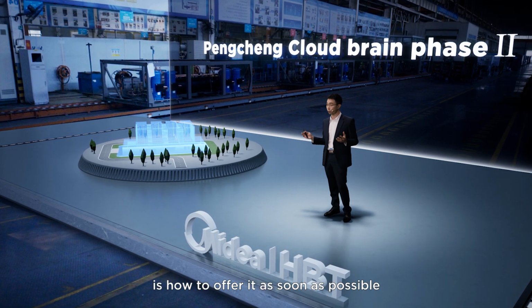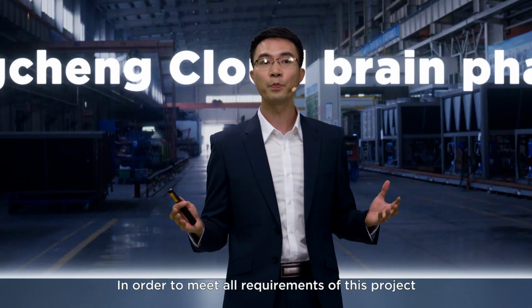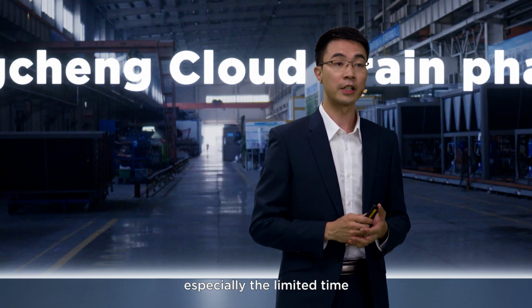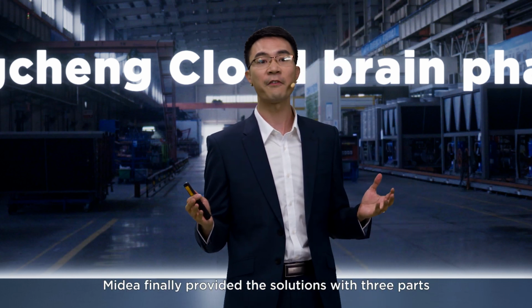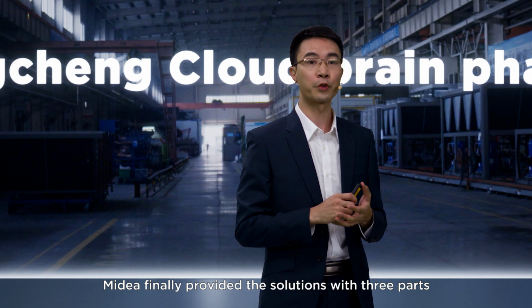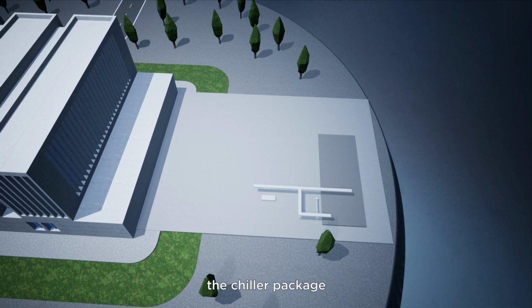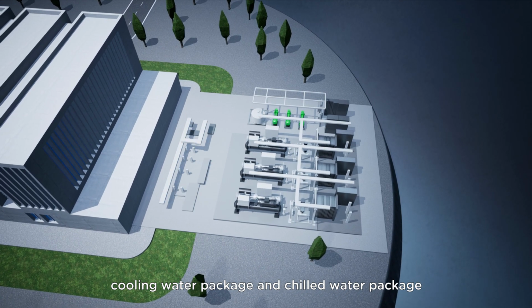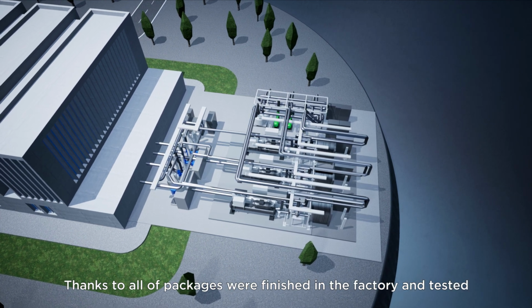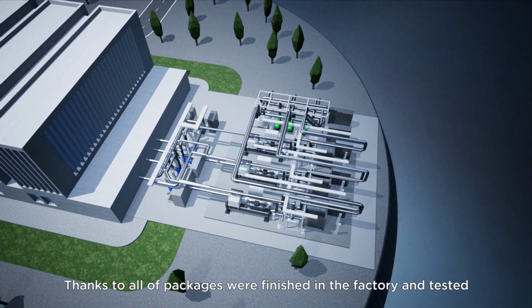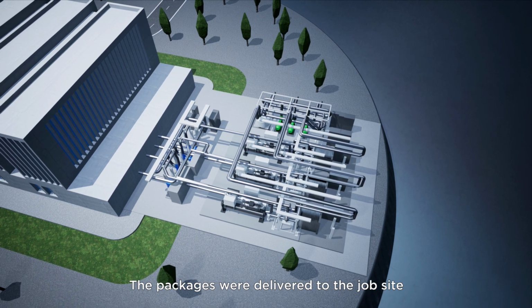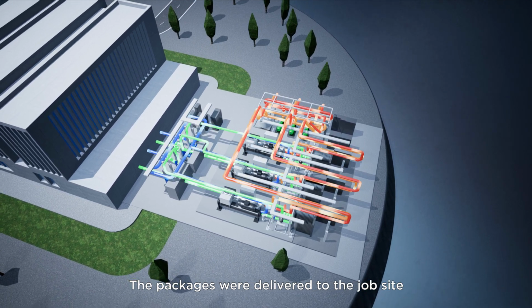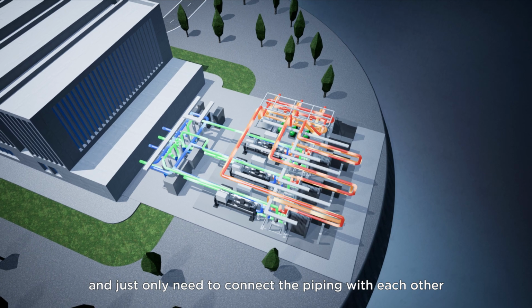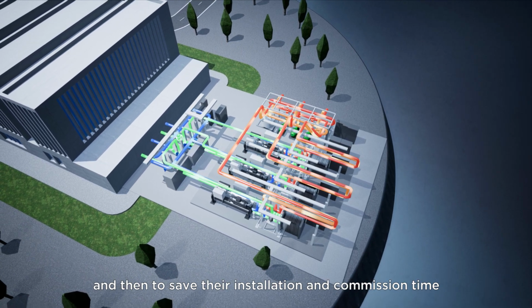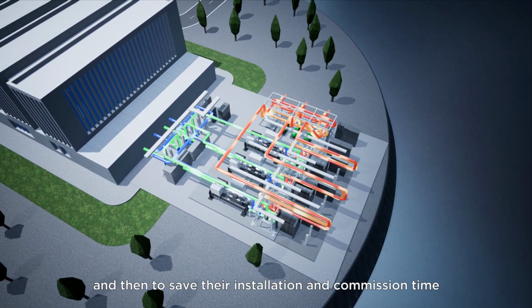Of course, low PUE, reliability, and free cooling are equally important. The challenge of this project is how to deliver it as soon as possible. In order to meet all requirements of this project, especially the limited time, Midea finally provided a solution with 3 parts: the chiller package, cooling water package, and chilling water package. Thanks to all the packages being finished and tested in the factory, they were delivered to the job site and only needed to be connected via piping, saving installation and commission time.